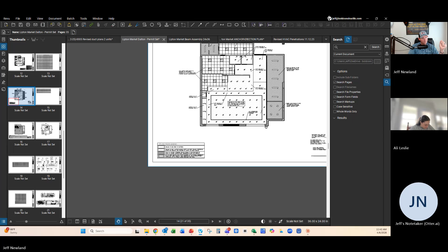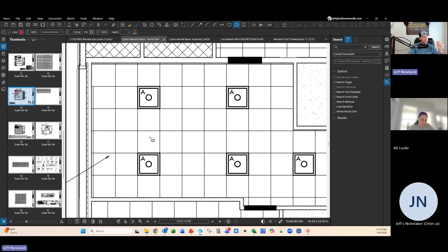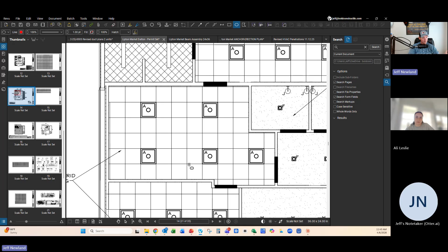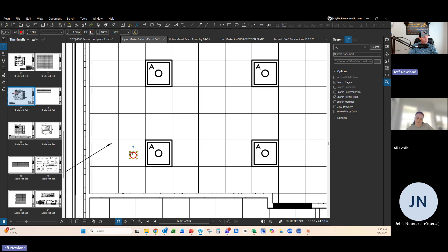So when we go to put a sprinkler in here, it just looks awful, and it's going to throw your grid off because we need to mark it. So what I typically do is have them mark on the ground where the diffusers go, where the light fixtures go, and where the sprinkler heads are going. That way when they mark it on the ground, we can transpose that mark up and see exactly where it's going to hit. Because ideally, whether it's a light fixture or whatever, you want it in the center of that tile if you can help it. Sometimes it's unavoidable, sometimes you don't have a choice, but it just looks a whole lot better when we do that.